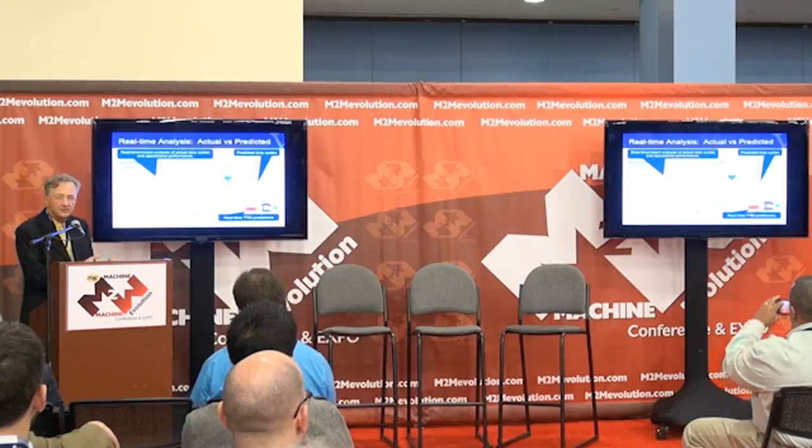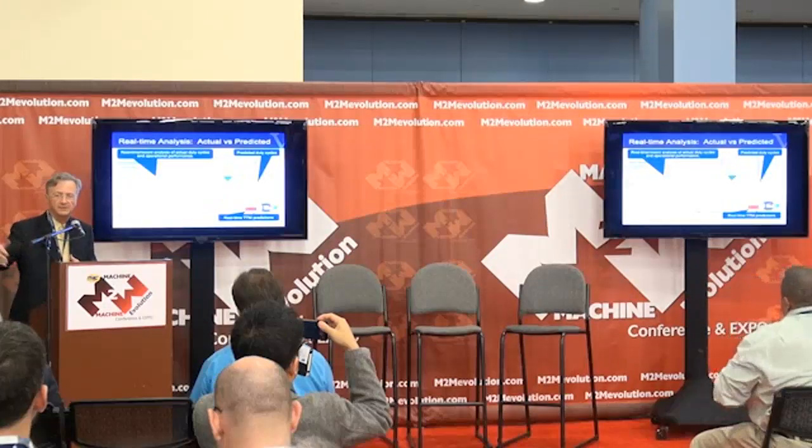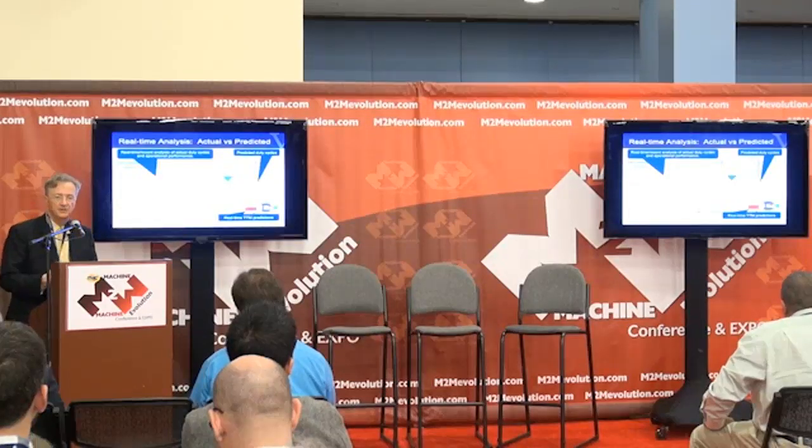Those notifications then go down to the fab. At any point in time you can drill into a piece of equipment to see more detailed granularity. In this case we drilled into equipment one, now showing eight hours of history behind and a few hours of predictive history ahead, shown in gray and red. The inset window pulls the actual and predictive together over the past few hours, immediately giving insight — in this case the laser is firing at a higher duty rate than predicted, which may explain the elevated temperature.